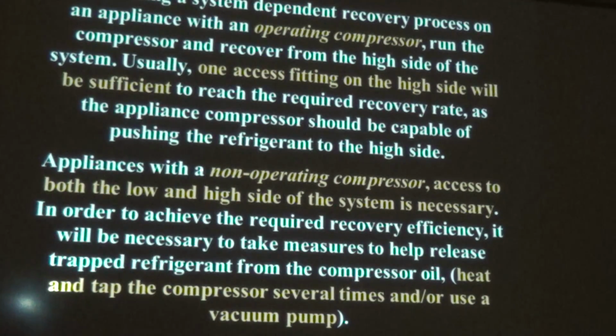When you use a system-dependent recovery process on an appliance that has a compressor that works, run the compressor and recover from the high side of the system. Usually one access fitting on the high side will be enough to reach the required recovery rate. That's at 4 inches of vacuum, as the appliance compressor should be capable of pushing the refrigerant to the high side.